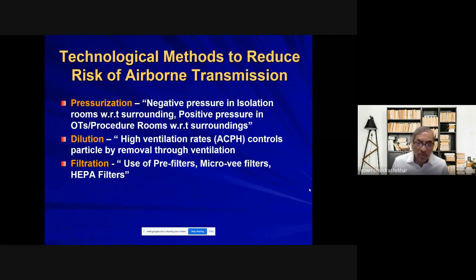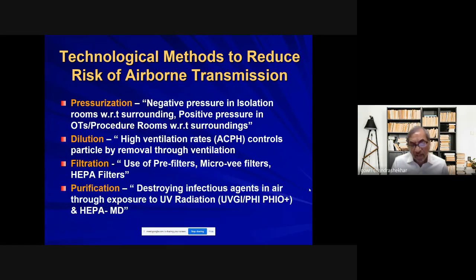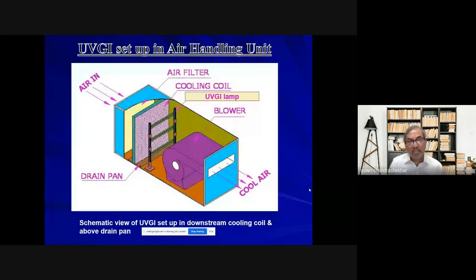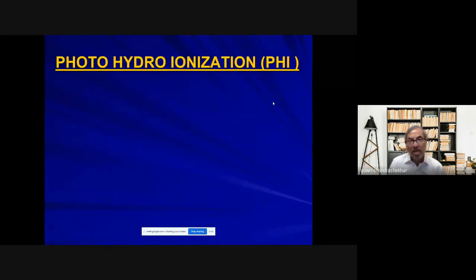The fourth one, which was very important, was purification. We always used to say a filter can trap the pathogen and there will be a colony of pathogens, but you will never kill them. So destroying infectious agents in air is done through exposure to ultraviolet radiation, or PHI, which is photohydroionization, or HEPA-MD. HEPA is high efficiency particulate arrestance, MD is microbial destruction. So when you see the AHU, you can add one UVGI lamp, which takes care of this destruction part, or the purification part.